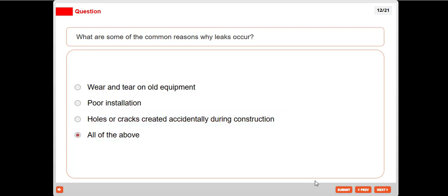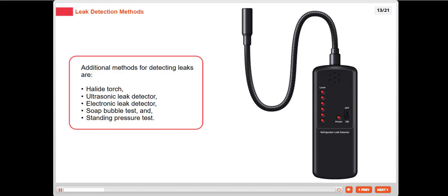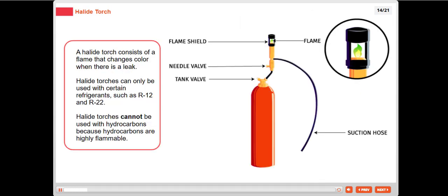Additional methods for detecting leaks are halide torch, ultrasonic leak detector, electronic leak detector, soap bubble test, and standing pressure test. A halide torch consists of a flame that changes color when there is a leak. Halide torches can only be used with certain refrigerants, such as R12 and R22. Halide torches cannot be used with hydrocarbons because hydrocarbons are highly flammable.